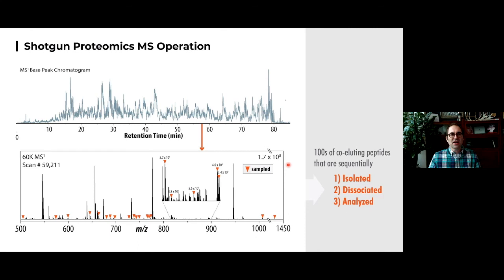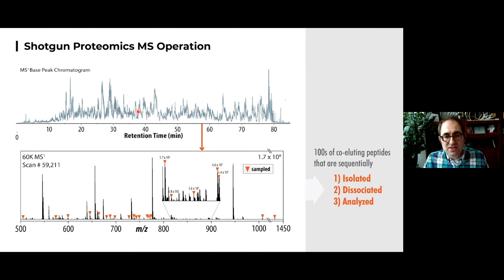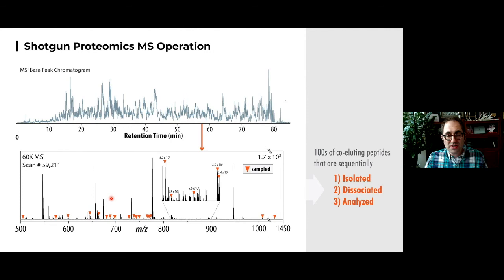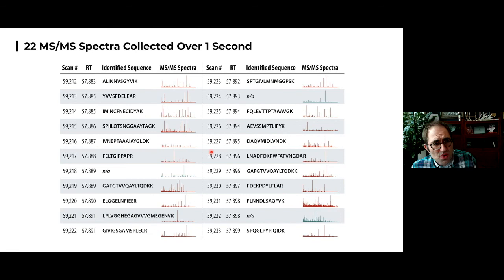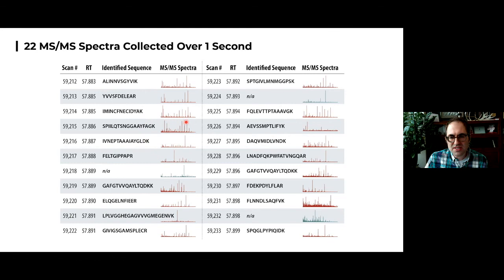In the context of a proteomics experiment: the LC chromatograph produces peaks of peptides eluting from the column. As they enter the mass spectrometer, it takes MS1 survey scans of all eluting peptides, then targets them one at a time for isolation, dissociation, and tandem mass spectral analysis. This process is very fast — 22 tandem mass spectra were collected in just over one second, about 20 per second. Over an hour and a half of analysis, we can collect tens or hundreds of thousands of tandem mass spectra.